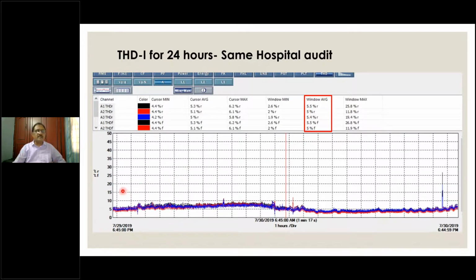As you can see here, for this one full day, the average harmonic current THD, total harmonic distortion, did not reach 8%. At that time, that was the standard. So this hospital was well within the 8%. So we certify saying that this hospital is not polluting the grid. So this is from the same one-day recording.